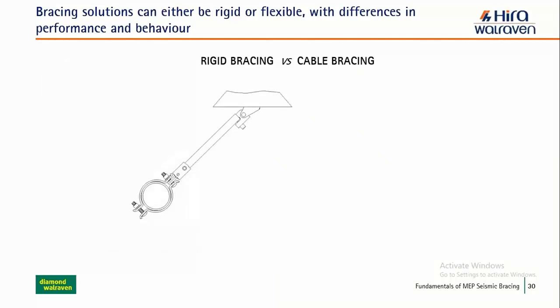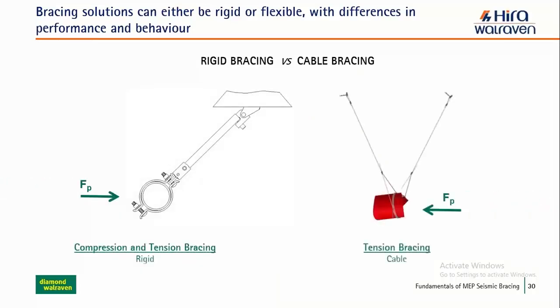Now comparing rigid bracing system with cable bracing system: the rigid bracing system is not flexible and involves channels to brace the system, so both compression and tension reactions occur. In the cable bracing system, only tension force occurs during a seismic event, or in terms of reaction, only tension.